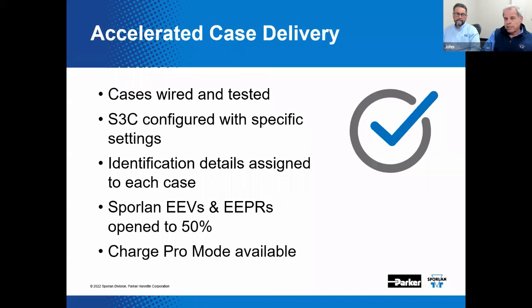Now, if the cases aren't wired up and powered, you can always use a magnet to open the solenoid valve if that's present, if the case has not been powered up, like we've said. If the case is wired and powered up, there's something called Charge Pro mode that is part of the control scheme, and you could use that to force the step motor valves to 100% open position. Yep. And the liquid line solenoid to an open position. That would include the circuit EEPR and that liquid line solenoid valve. So that would be a handy thing. That's a way to force everything wide open. So that's that Charge Pro mode, and we will tell you more about that at another time.